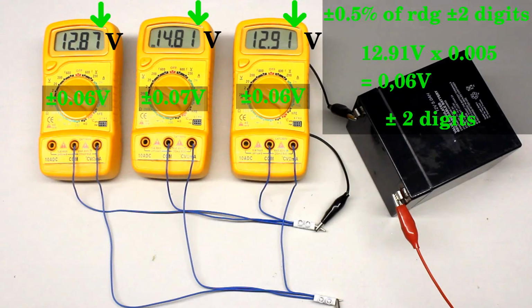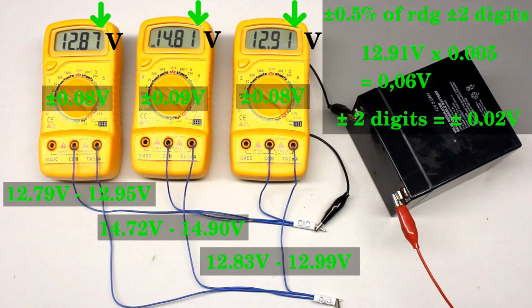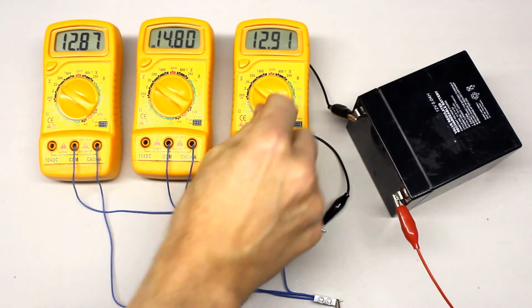A digit, strictly speaking, the least significant digit is the lowest decimal place of the reading. In the 20 volts range, 1 digit corresponds to 0.01 volts, hence 2 digits correspond to an error of 0.02 volts. Thus, the total error is plus minus 0.08 volts.